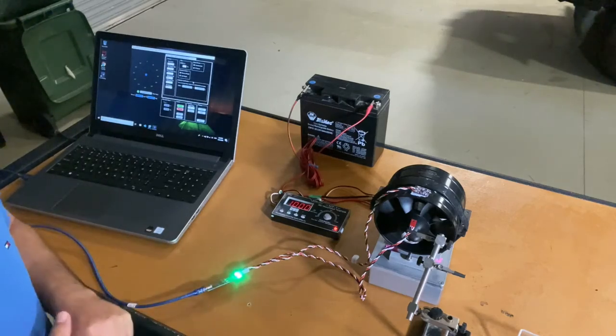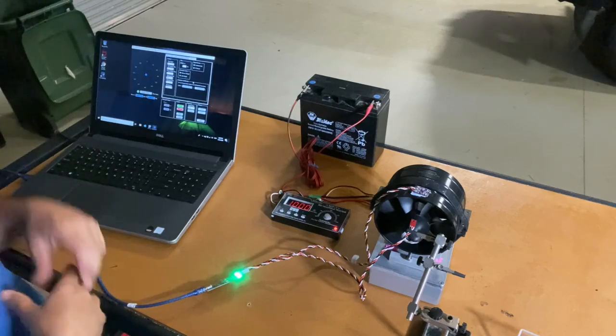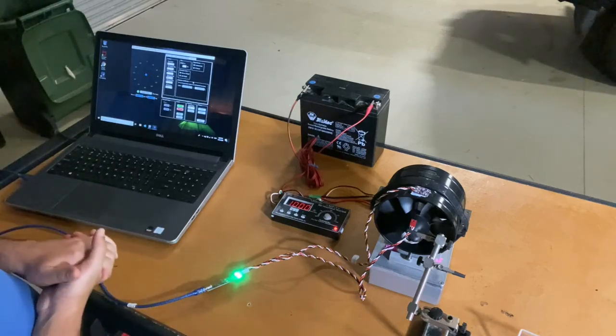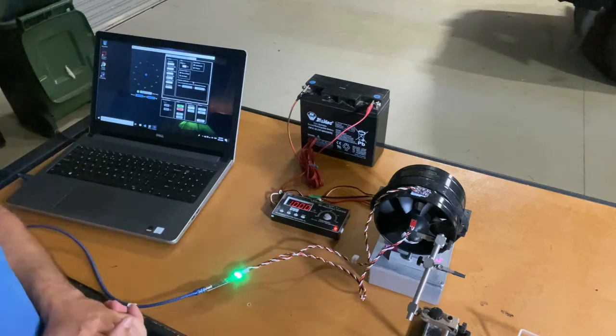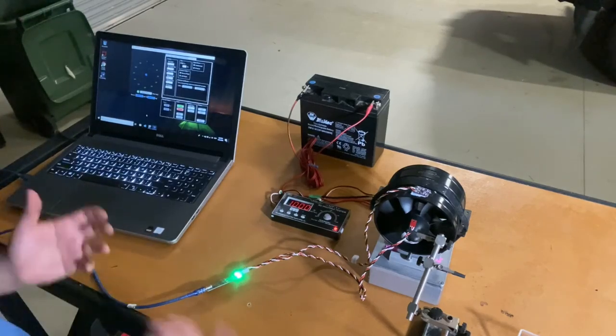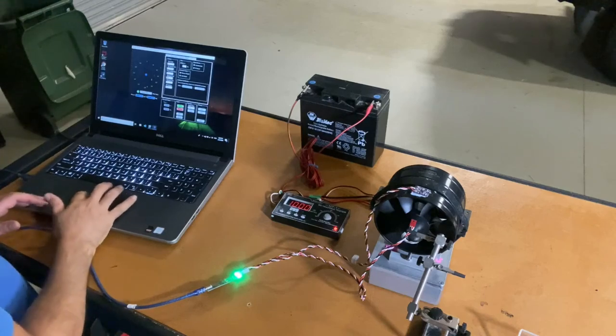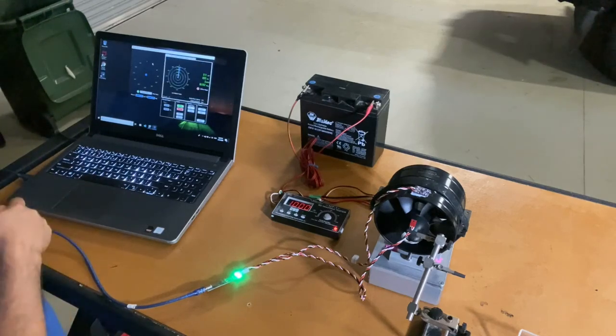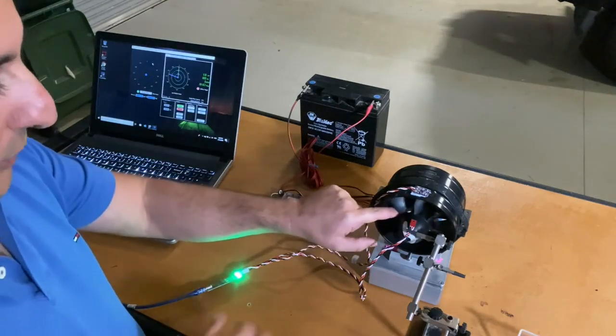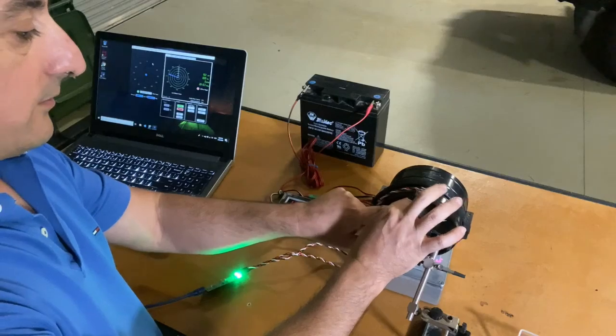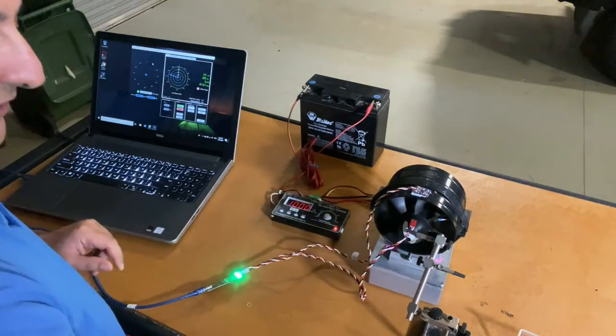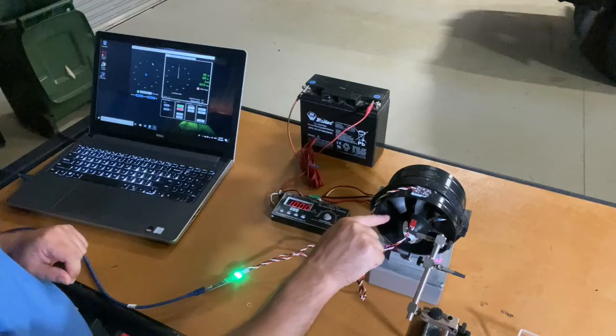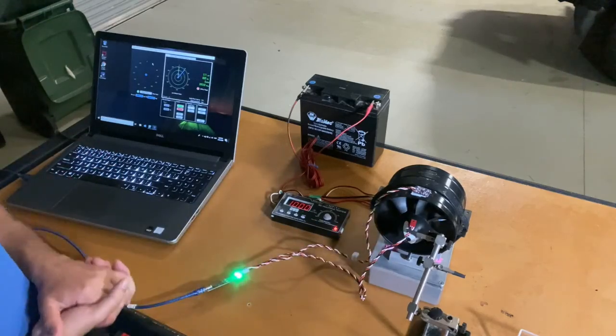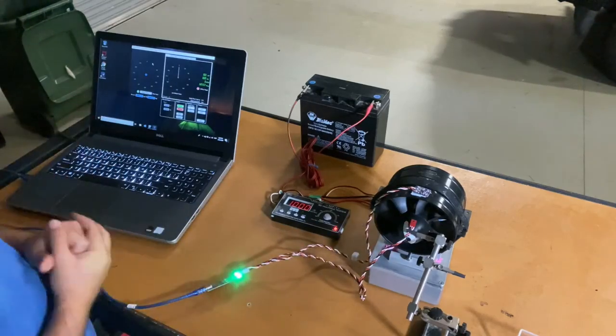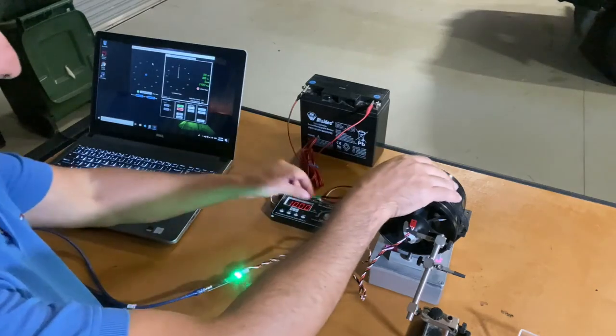Alrighty, so now we've actually got our system calibrated, set up, ready to go. Now we're going to do our balance run. To do our final balance run, we'll switch back to the live window, and we'll make sure that our trial weight is removed. We don't need that anymore because the system is calibrated. And we're going to run the EDF at the test speed and measure the vibration level.